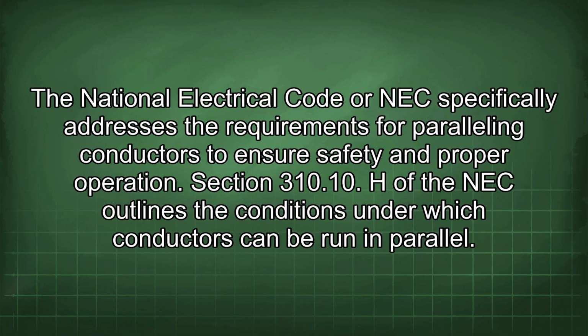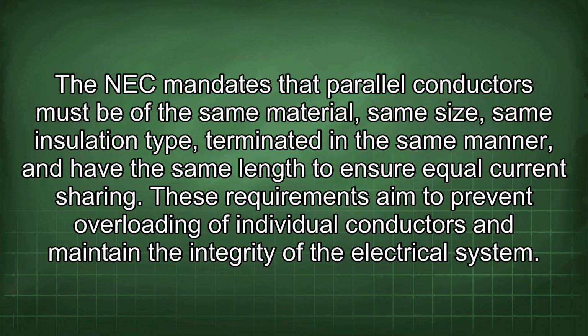The National Electrical Code, or NEC, specifically addresses the requirements for paralleling conductors to ensure safety and proper operation. Section 310.10(H) of the NEC outlines the conditions under which conductors can be run in parallel. The NEC mandates that parallel conductors must be of the same material, same size, same insulation type, terminated in the same manner, and have the same length to ensure equal current sharing. These requirements aim to prevent overloading of individual conductors and maintain the integrity of the electrical system.